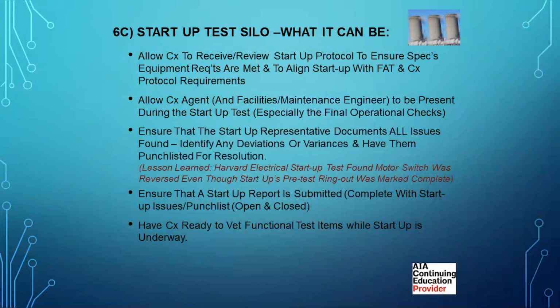So what it can be is, again, all of these things can work together for integration. If you're looking at the protocol for startup, you could say, wait a second, this doesn't match the spec requirements. I have seen startup protocols provided to me that are almost basically a blank sheet of paper. And I said, wait a second, where does it show that you've identified that you're meeting this voltage requirement? That it's not just qualitative, yeah, it works good.